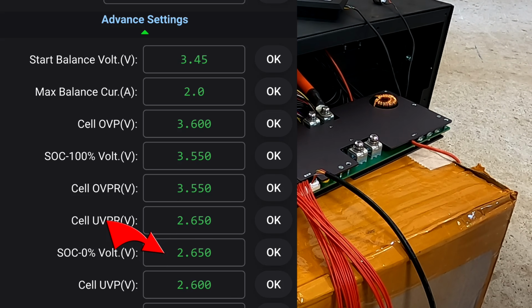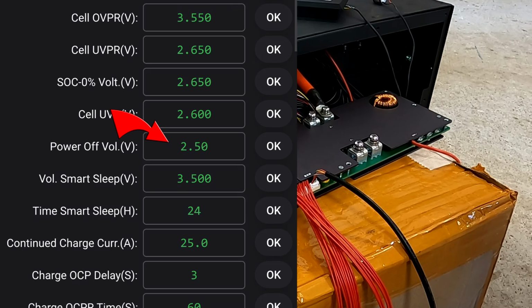And you can see further down below here, it also has a state of charge of 0% at a voltage of 2.65 volts. This is also when the BMS will show you a 0% state of charge. So in between we have the cell over voltage protection recovery. It's 3.55 as per default. And we also have the cell under voltage protection recovery at 2.65 volts. The cell under voltage protection kicks in at 2.6. We also have a power off voltage of 2.5.